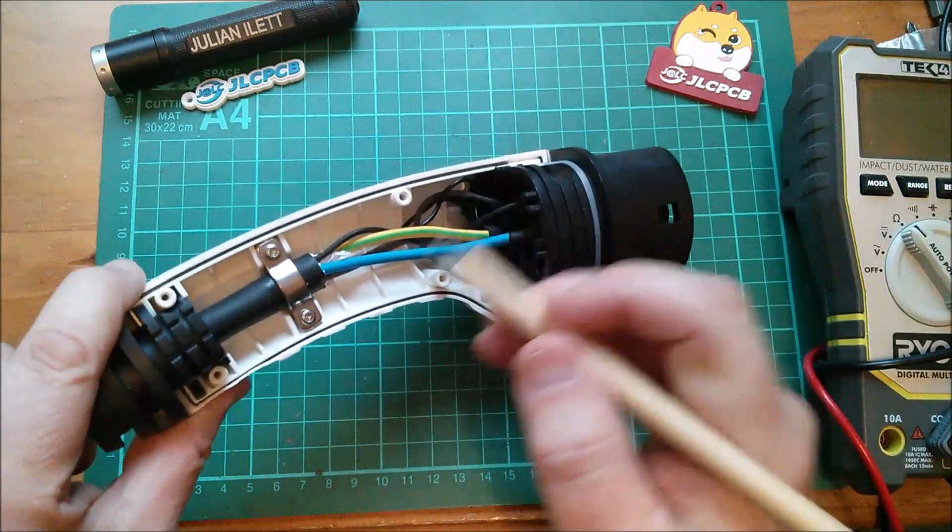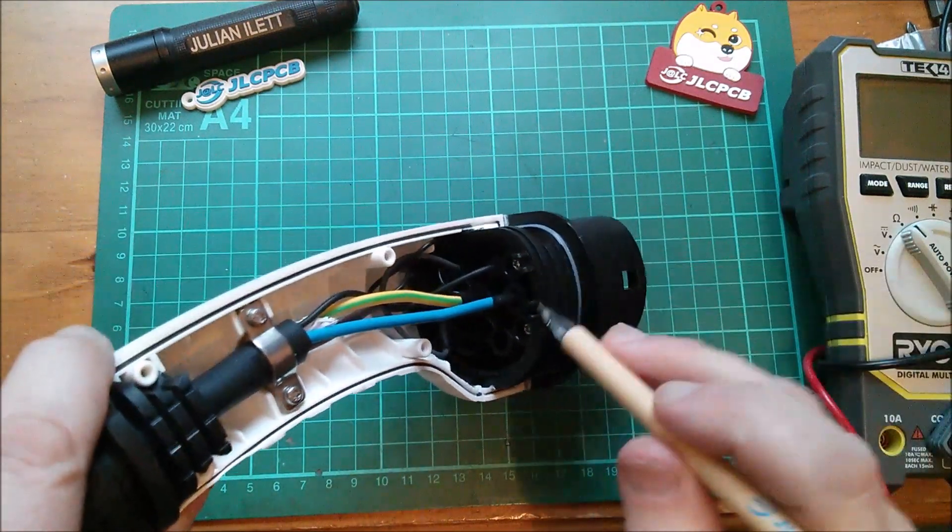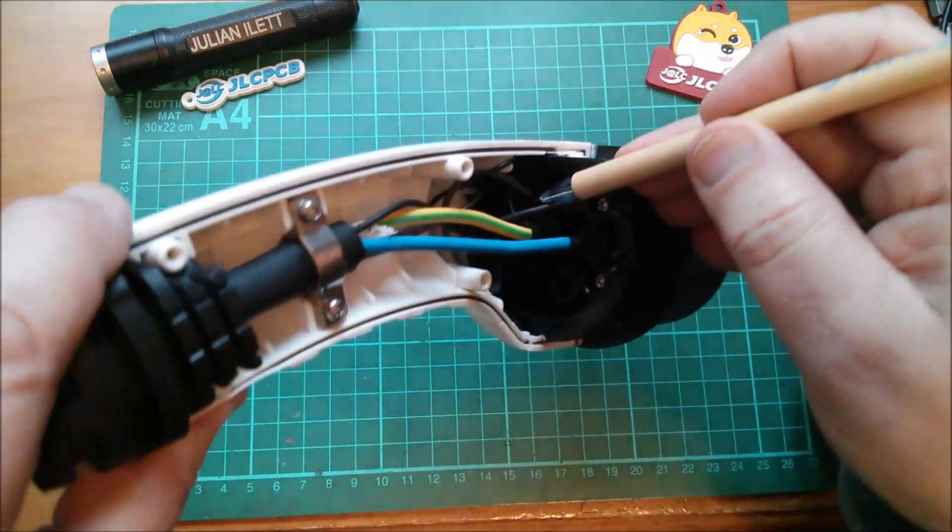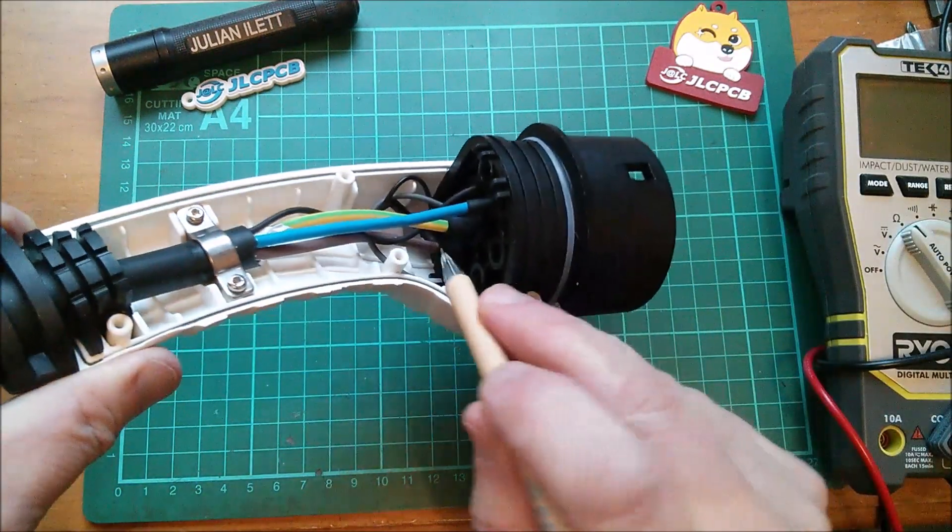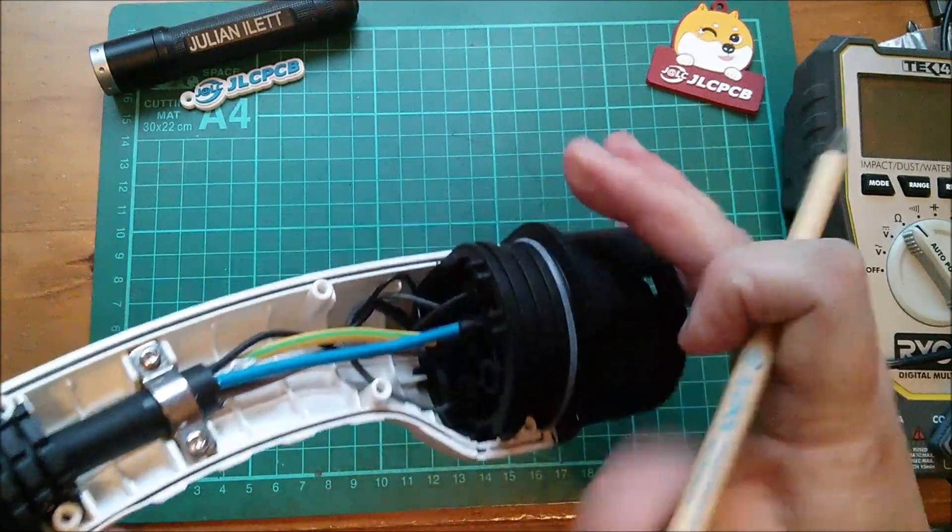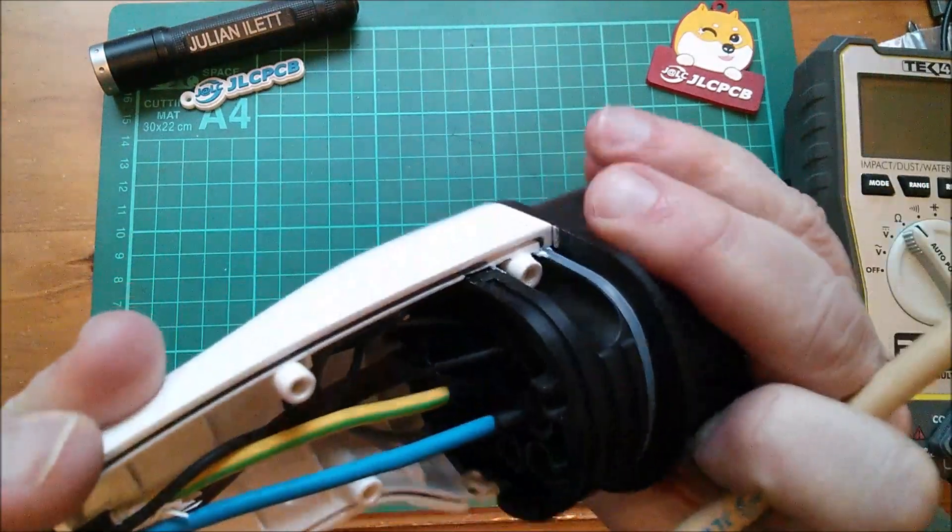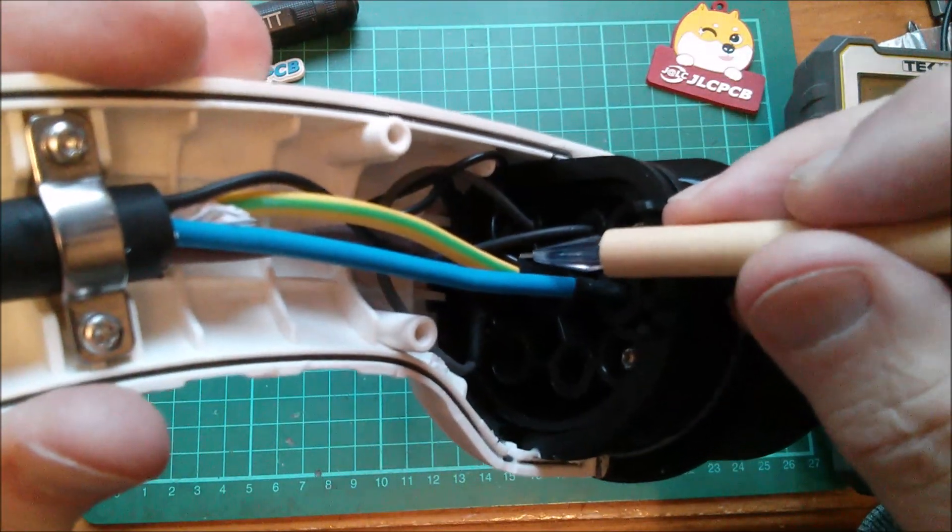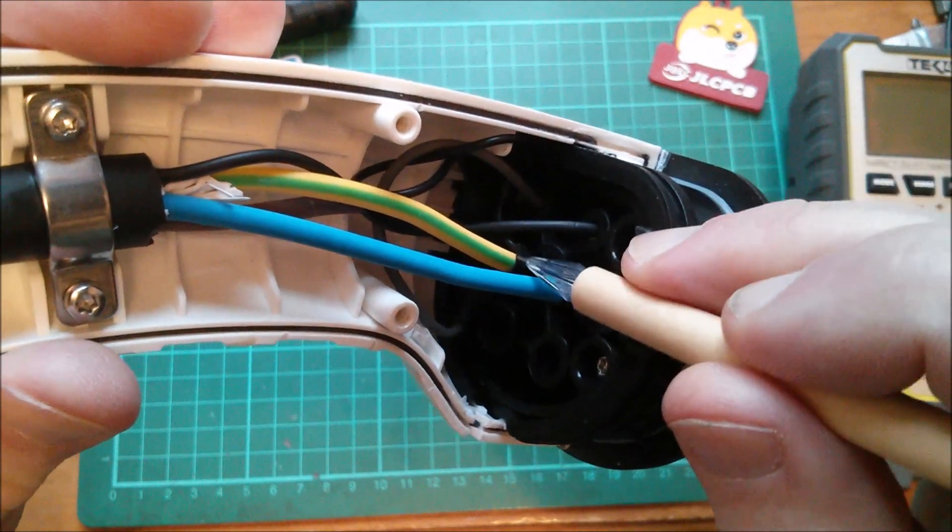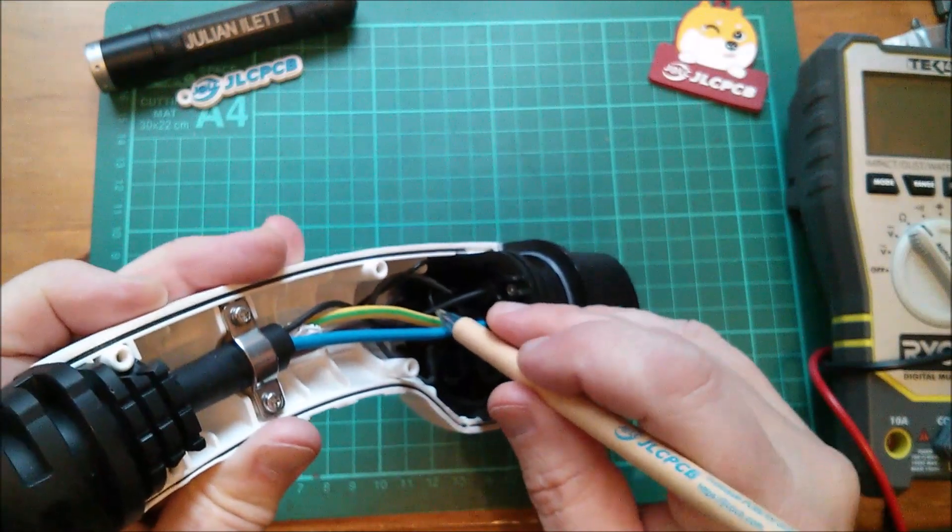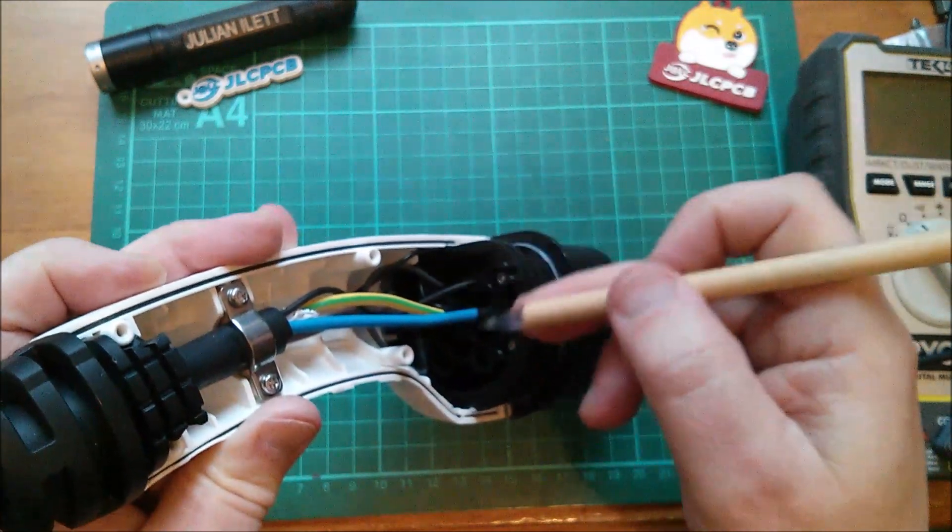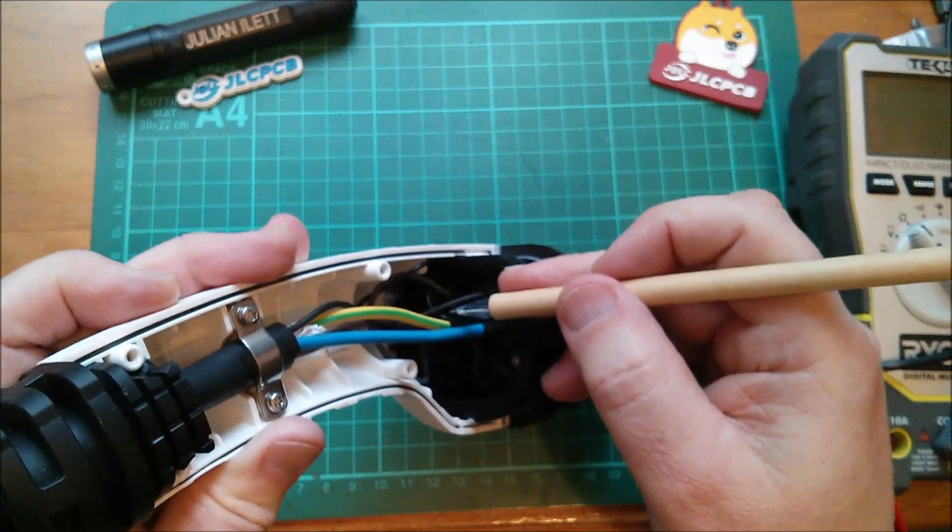But what you can see is that there's gray wire coming out of the PP connector, which is there. It sort of loops around, goes to a bulge in a bit of heat shrink and then goes in with, I don't know whether you can see this very easily, but you can just about see a wire coming around there and going in with protective earth. So that's the resistor linking PP through a 680 ohm resistor. We measured that to protective earth.